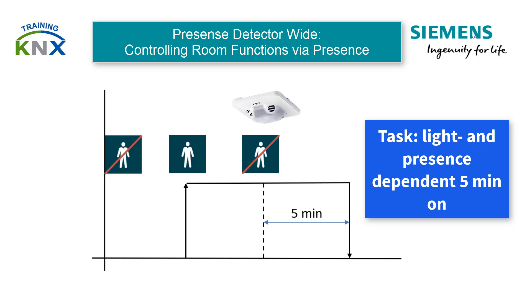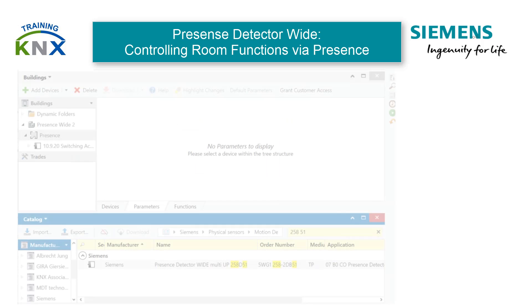The task for the fully automatic system is to switch on the room lighting without delay and brightness dependent when individuals are detected in the room. It should remain switched on as long as there are people in the room, and switch off again automatically with an overshoot time of 5 minutes after the last person has been detected, for example. For the configuration, we proceed to ETS now.